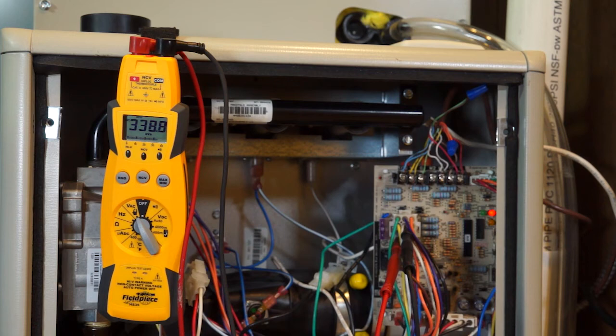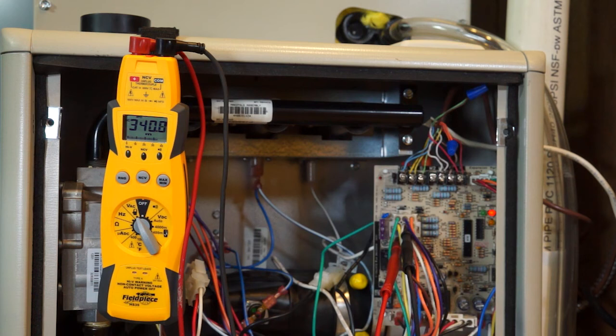high resistance in the circuit can make circuit boards do really weird things. But if you look at the lights now, we have an alternating flash between the green and red lights. That is one hour lockout.